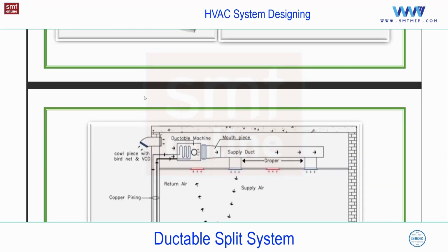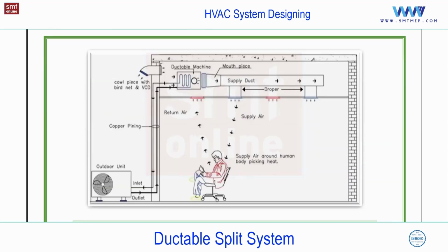So you see how this ductable system works. Very simple. Everyone is aware of the split system, na? And what are the components in indoor and outdoor? The same thing in this, because it's a ductable split. So this is the outdoor unit, this is the indoor unit, but this indoor unit is a ceiling suspended one. We can hang it with anchor fasteners like this, above the false ceiling, or it can be without false ceiling, with open ducting. You'll find in some supermarkets, it is visible. So the indoor unit has the option to attach the duct, because it's a ductable.